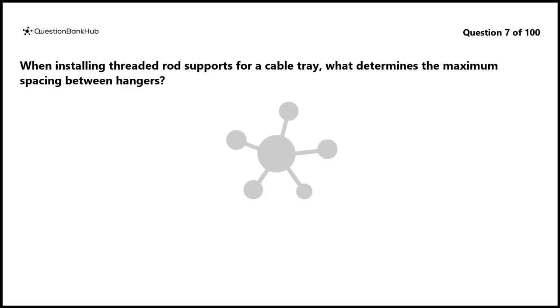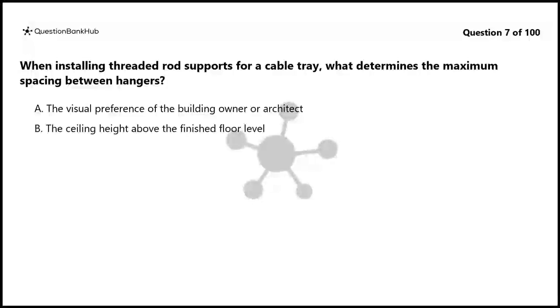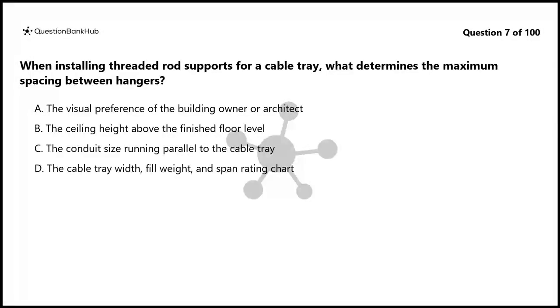Question 7. When installing threaded rod supports for a cable tray, what determines the maximum spacing between hangers? A. The visual preference of the building owner or architect. B. The ceiling height above the finished floor level. C. The conduit size running parallel to the cable tray. D. The cable tray width, fill weight, and span rating chart.